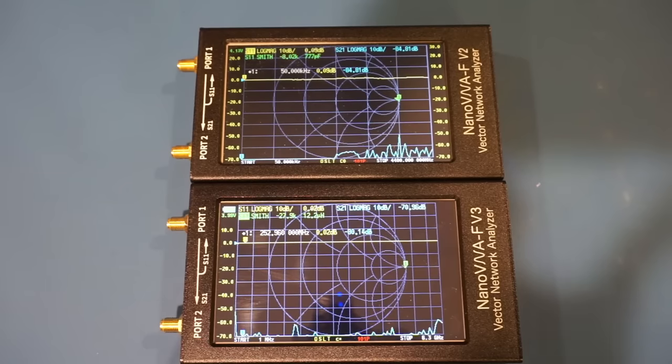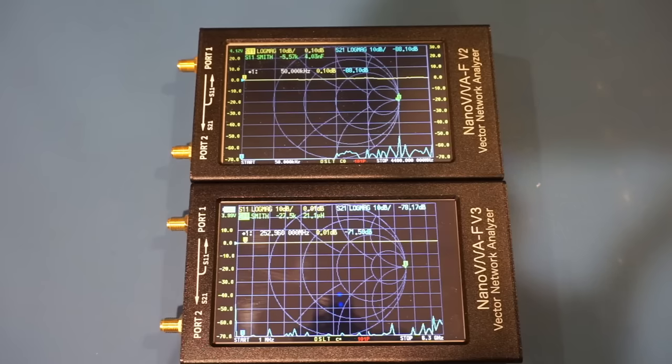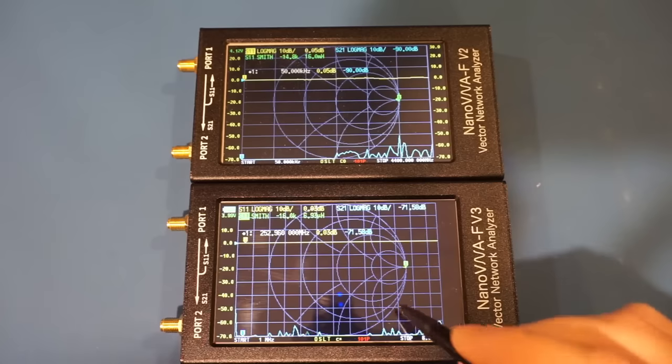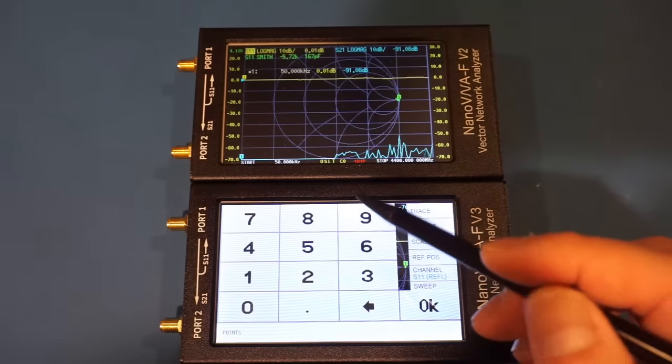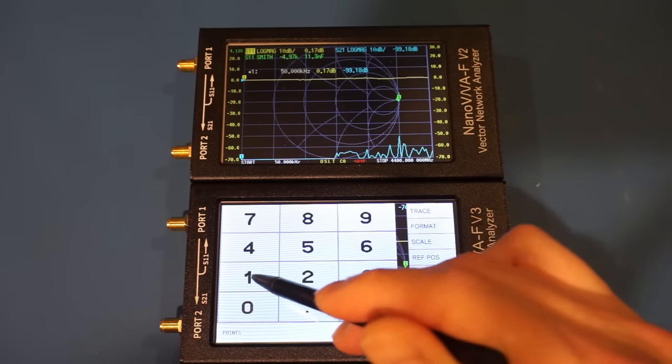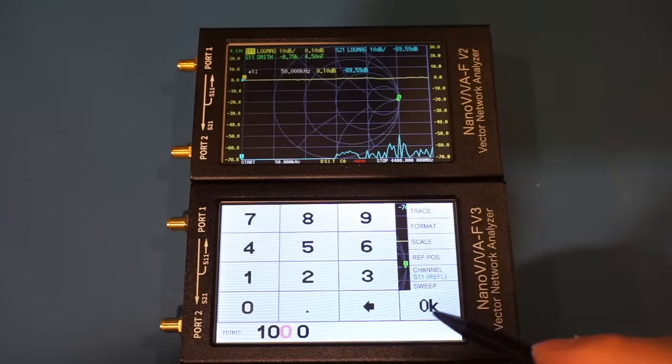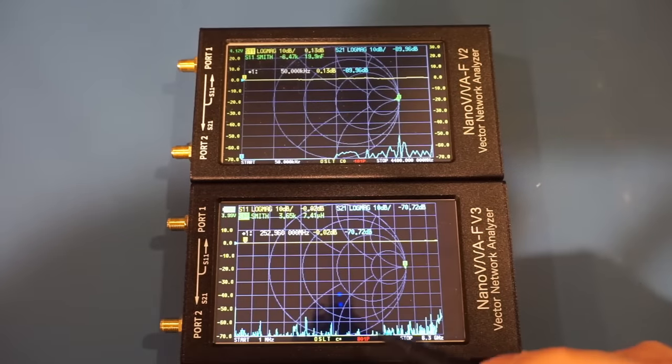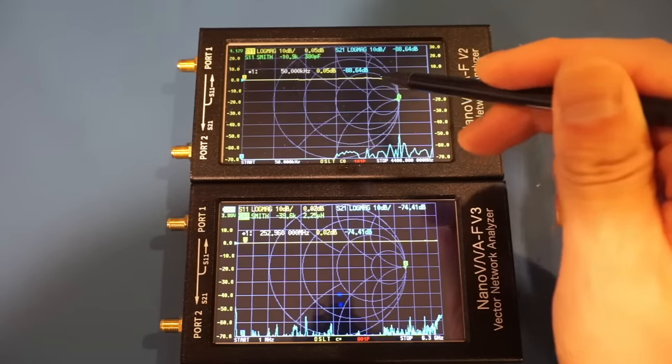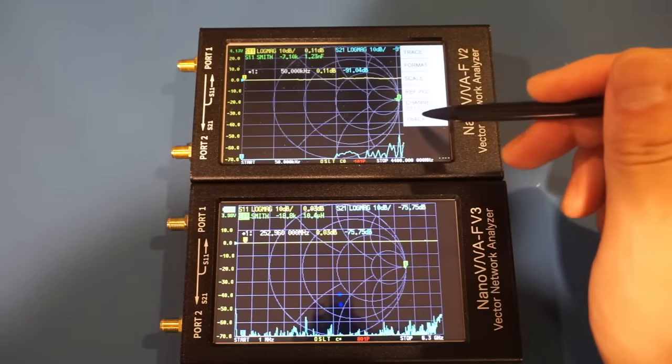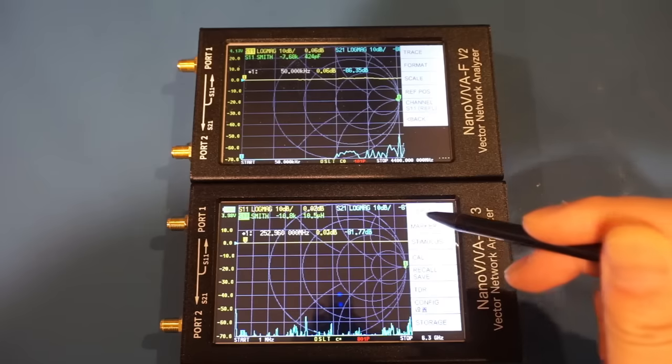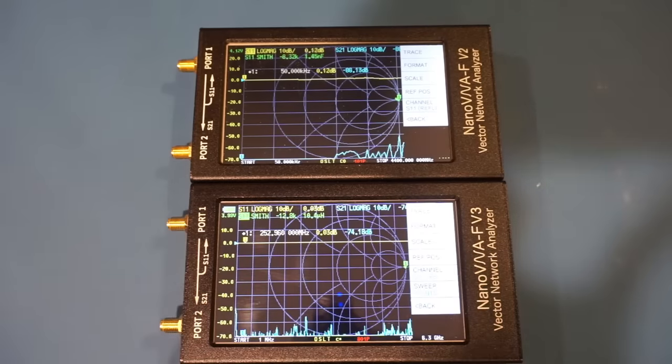Another thing worth mentioning is that with the V3, you can specify the number of points used per scan. You can set it all the way up to 801 points. If you just set a random number here, as long as it's above the maximum, it will automatically change to the maximum it supports. So here is 801. And if you notice on the V2, we actually don't have that menu option.